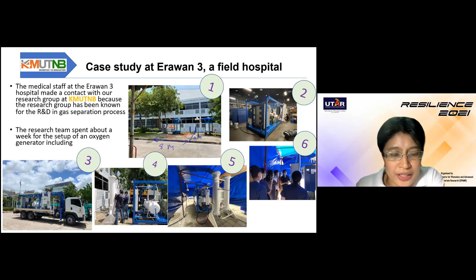The main units of the oxygen generator system consist of an air compressor, air receiver tank, air dryer, and desiccant. Through these units, the air will be compressed to high pressure and dried enough, so it has good quality to send to the oxygen generator. The oxygen generator will separate oxygen and nitrogen from the compressed air, and the oxygen produced will be sent to an oxygen receiver tank.